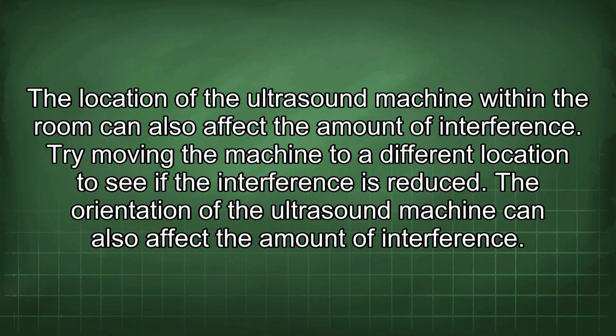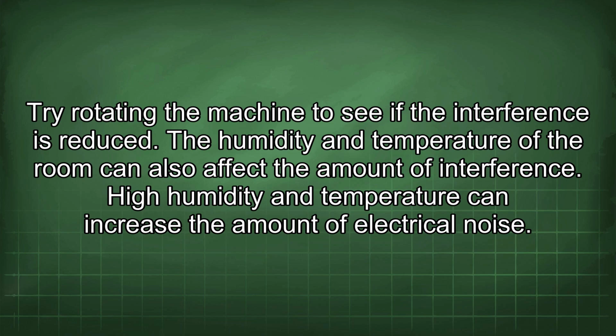The location of the ultrasound machine within the room can also affect the amount of interference. Try moving the machine to a different location to see if the interference is reduced. The orientation of the ultrasound machine can also affect the amount of interference. Try rotating the machine to see if the interference is reduced.